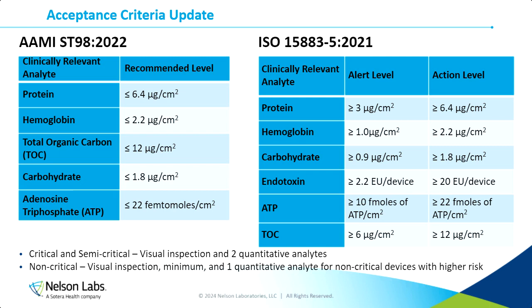Surrounding acceptance criteria, as you can see, there are protein, hemoglobin, total organic carbon, carbohydrates, and ATP. These are the criteria outlined in AAMI ST98, and they are also outlined in ISO 15883-5. One thing to keep in mind during your cleaning validations, as you're gathering your results for submission, is the alert levels in ISO 15883. So just keep that in mind when you're looking. There are alert levels that are established, but the action level is not reached until it would exceed that criteria.